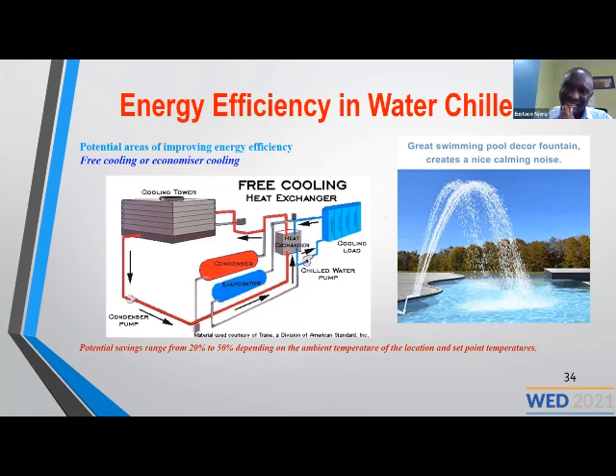The other question was: have you done remote monitoring on chiller parameters, and which specific parameters do you monitor? Yeah, in water chillers, the parameters normally monitored are the power consumption at any given time, vis-a-vis the temperatures. Those are mainly the parameters you measure: the temperatures of the areas being cooled, the temperatures of water, temperatures around the cooling towers, and the temperatures of the refrigerants. So you can do remote monitoring on all those.